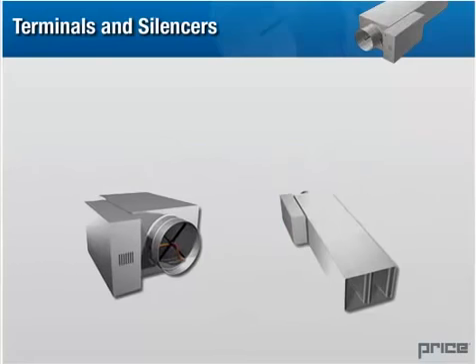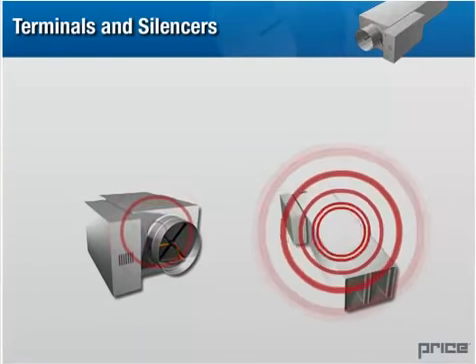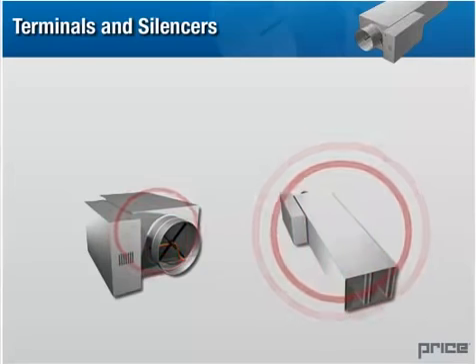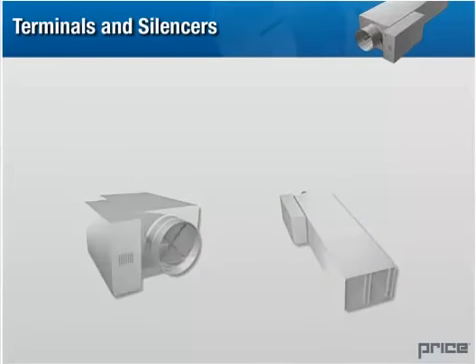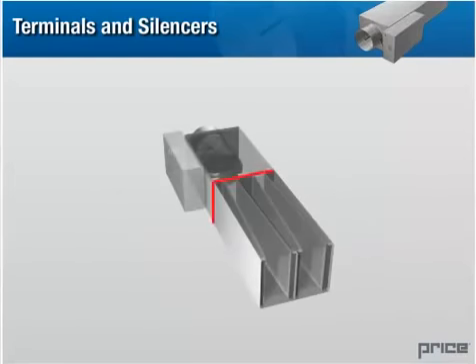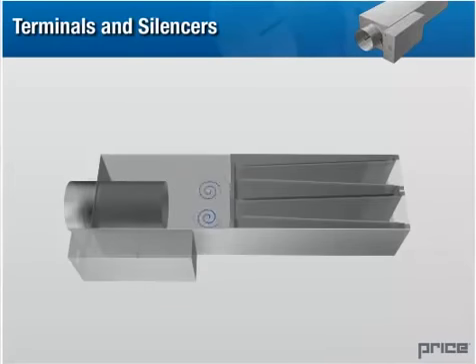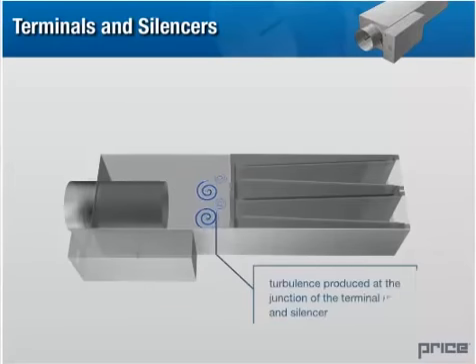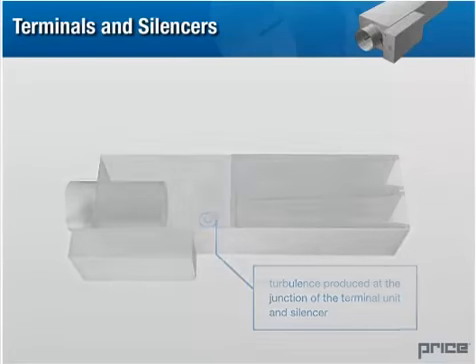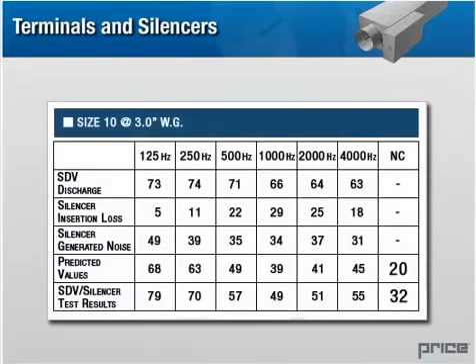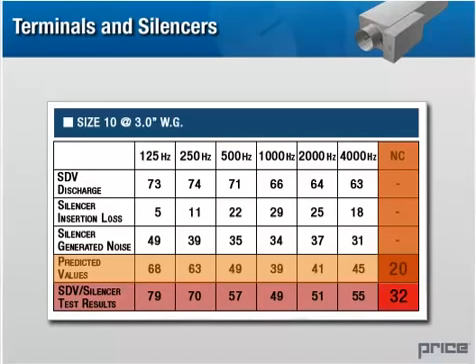In some cases, the terminals tested with silencers directly on the outlet are actually louder than the terminal unit alone. This is caused by the physical relationship of the internal geometry of the silencer and the airflow patterns produced by the terminal unit itself. As you can see, the predicted NC value for the space is NC20 and the actual test result is NC32. These values are considerably different and can adversely affect the engineer's design.